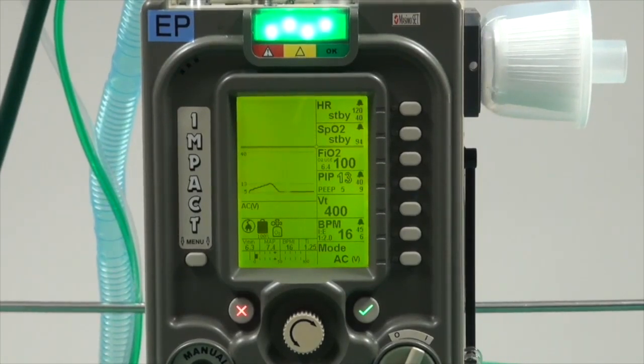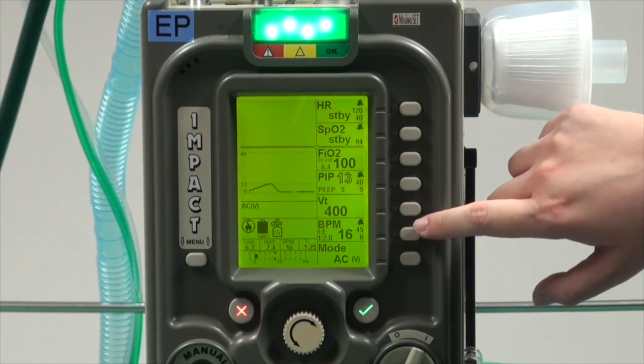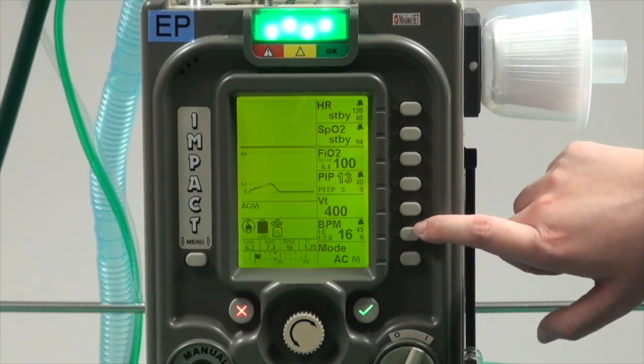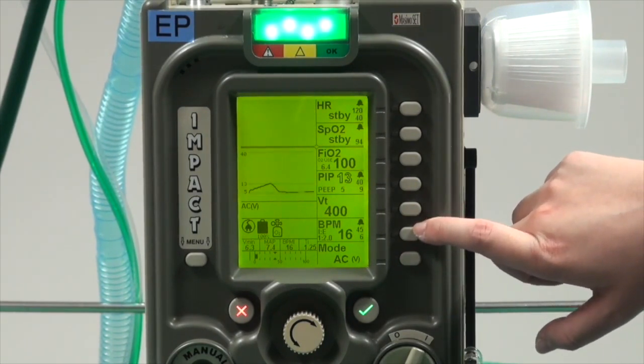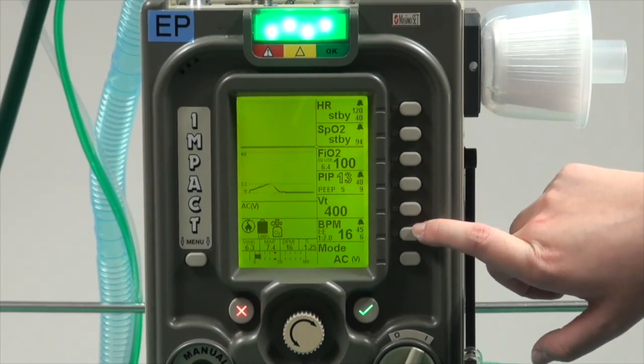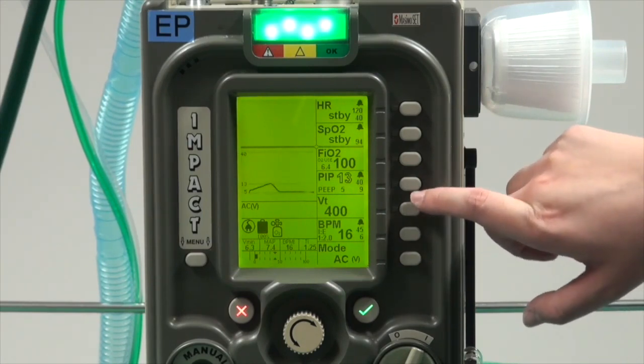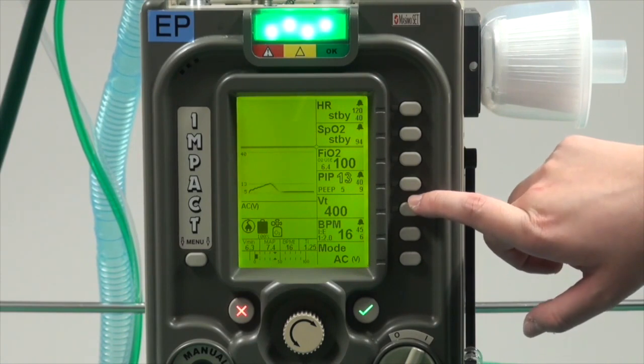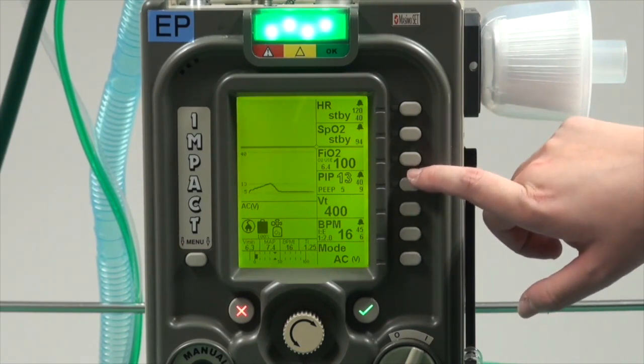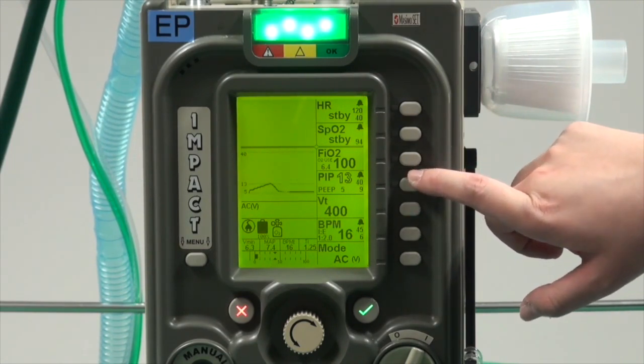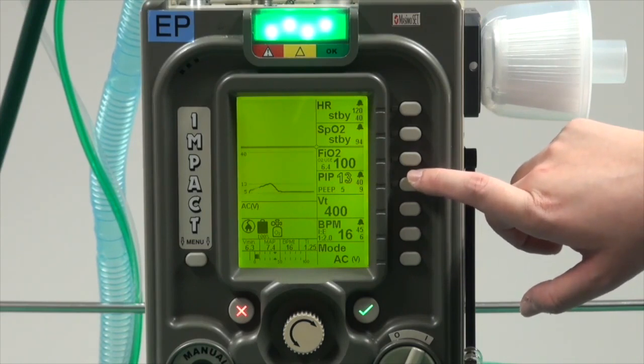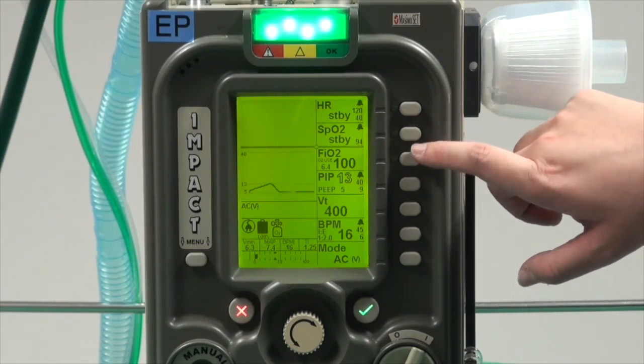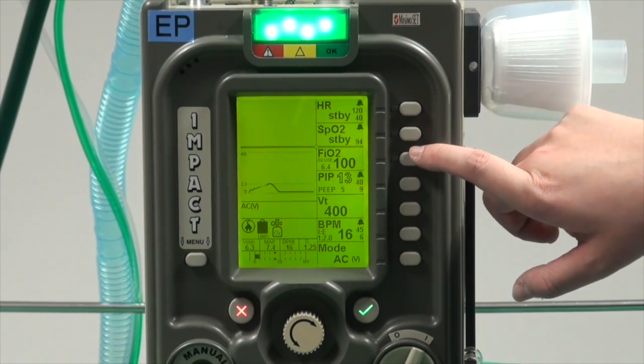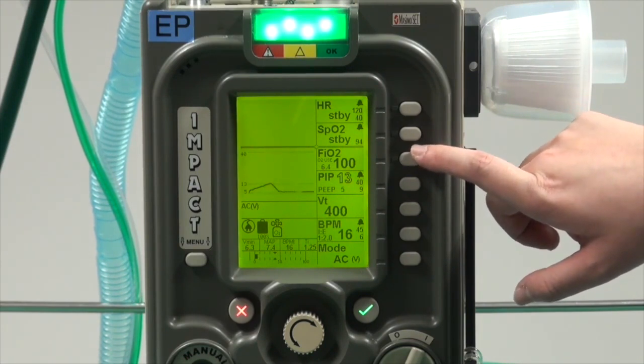Now your ventilator is in AC-VC mode. Set respiratory rate is 16, I to E ratio of 1:2. Frequency alarm limits are 45 and 6. Tidal volume is set at 400. Peak inspiratory pressure is 13. PEEP is set at 5. Alarm limits are set at 40 and 9. And FiO2 of 100%.